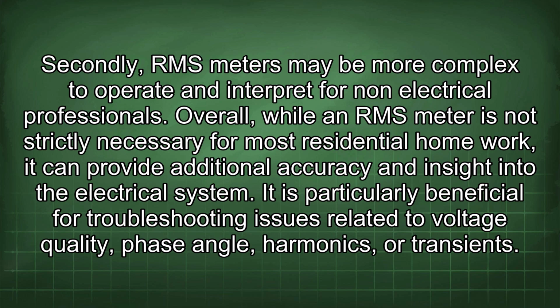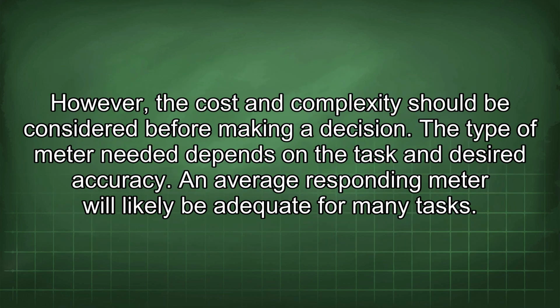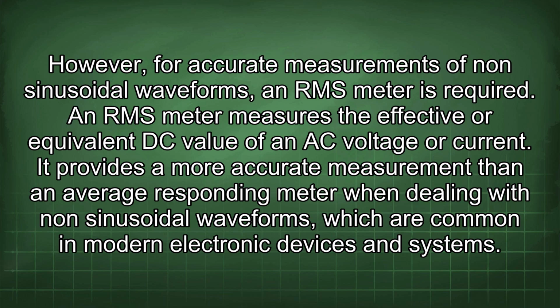It is particularly beneficial for troubleshooting issues related to voltage quality, phase angle, harmonics, or transients. However, the cost and complexity should be considered before making a decision. The type of meter needed depends on the task and desired accuracy. An average responding meter will likely be adequate for many tasks. However, for accurate measurements of non-sinusoidal waveforms, an RMS meter is required.